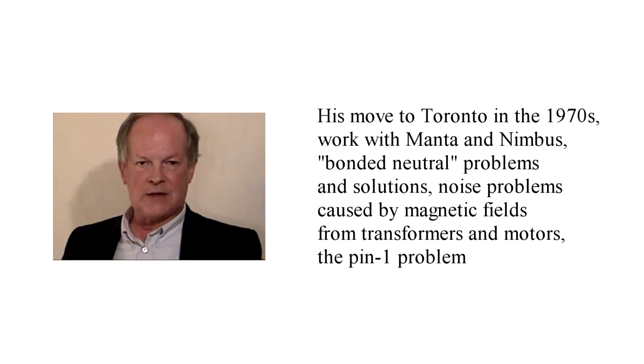Now that is a lightning prevention, that's your last line of defense against lightning. Because prior to that, theoretically, there's going to be a transformer that'll block most of it, but that's your last line of defense. You can't build a building without a neutral bonded at the service entrance, and that's in the code, both here in the States. But anywhere else in the building, you're going to use the same panel, which they do all the time, and you have to take that bonding screw out.